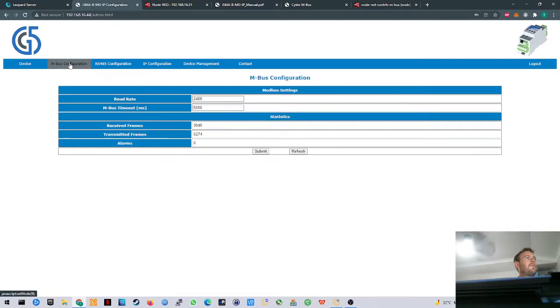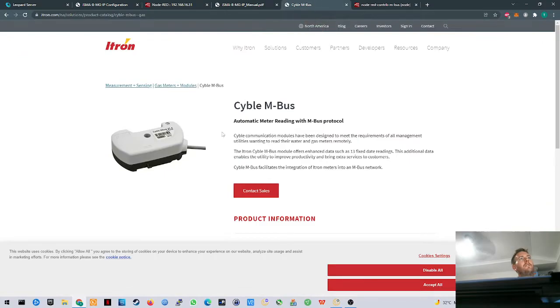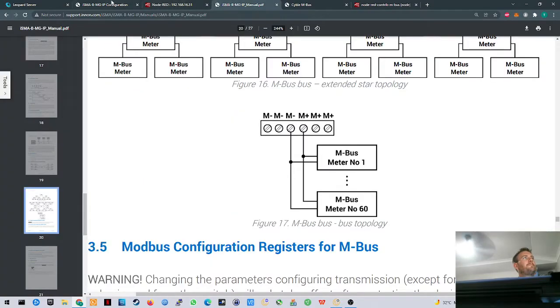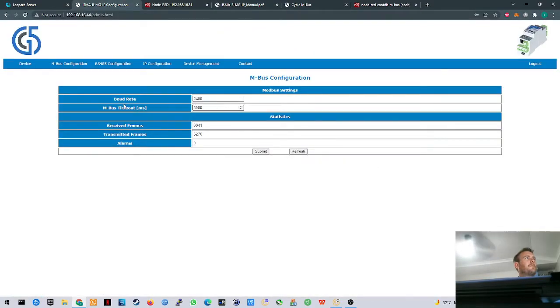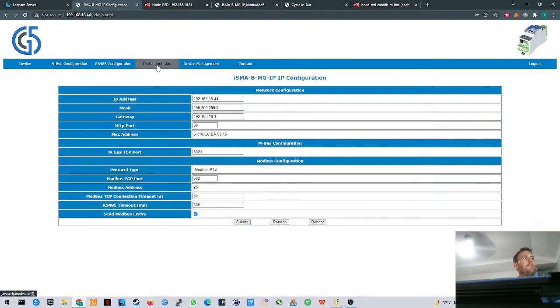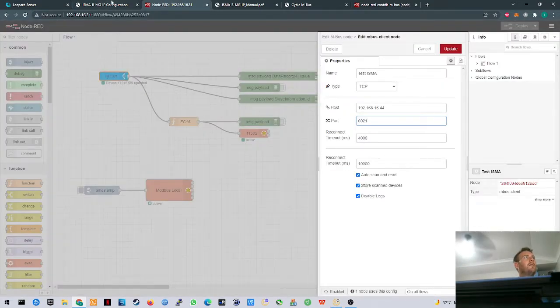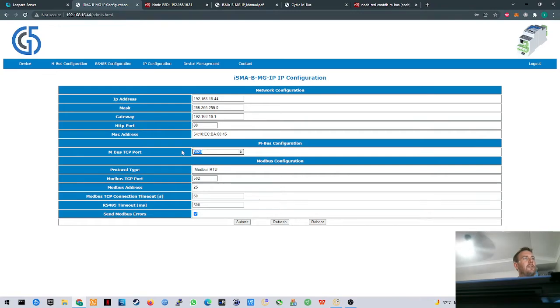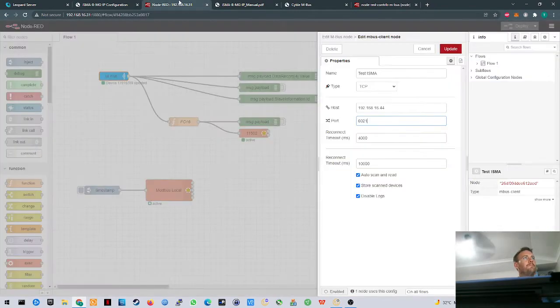So on the MBus side, you've got to match the baud rate to the default baud rate on your Cybles, 2400. Give it a timeout, and then from there you just need to make sure you know which port this is. I think the default was like 10,000 on Node-RED, and default here is 6021. So I just updated that, making sure that all that was running.